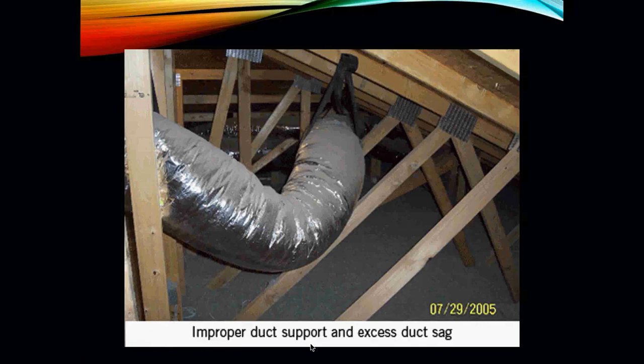This is what we mean by improper duct support. We have excessive sag in there. As that air is coming out of this particular flex duct, it is hitting turbulence right here. It's slowing down because now it has to sag down. It's hitting this turn, and then it has to climb back up again. This is improper. We do not want to see this type of installation. If it is, we can fix it.